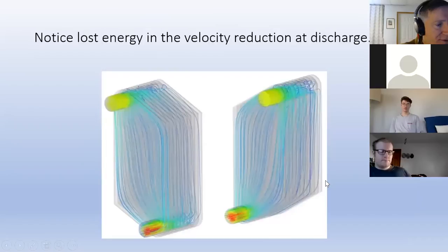This is flow through a heat exchanger. It's like a radiant heat exchanger. If you look at the direction of how things flow, you can see you have higher velocity at the bottom than at the top, so it's helping you get an idea of which way things are flowing. When you do computational fluid dynamics, you can plot things like streamlines, lines that particles follow, velocity, temperature, the resident time of the particles. This is the same sort of numerical method we've looked at briefly with finite element analysis, but it's doing it for fluids, so gases and liquids. Here you can see the low velocity in the radiator or heat exchanger, and the higher velocities in the tube. If you're pushing a certain amount of air or water and you put it in a smaller area, it's got to go faster.